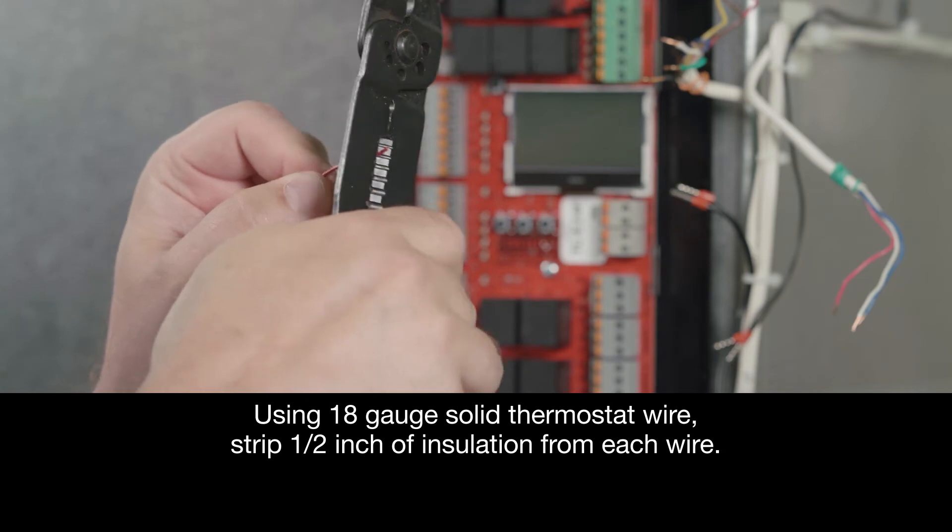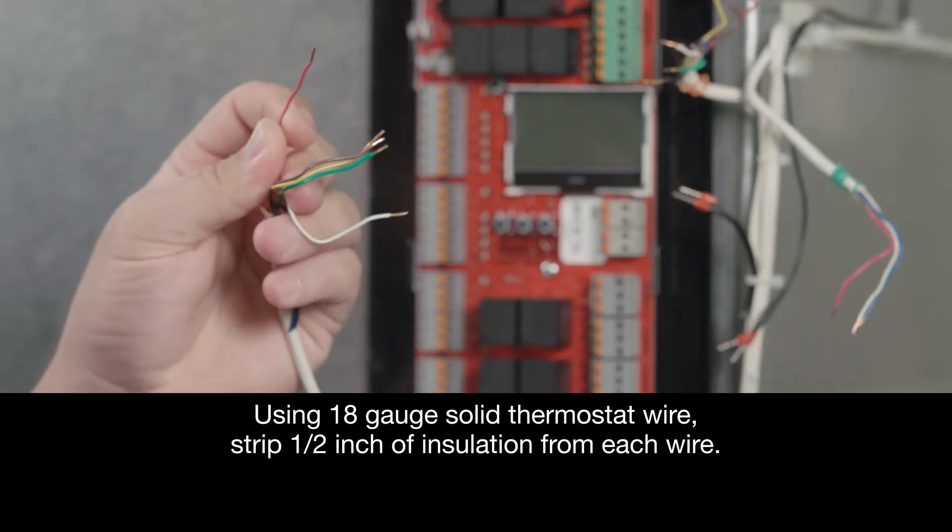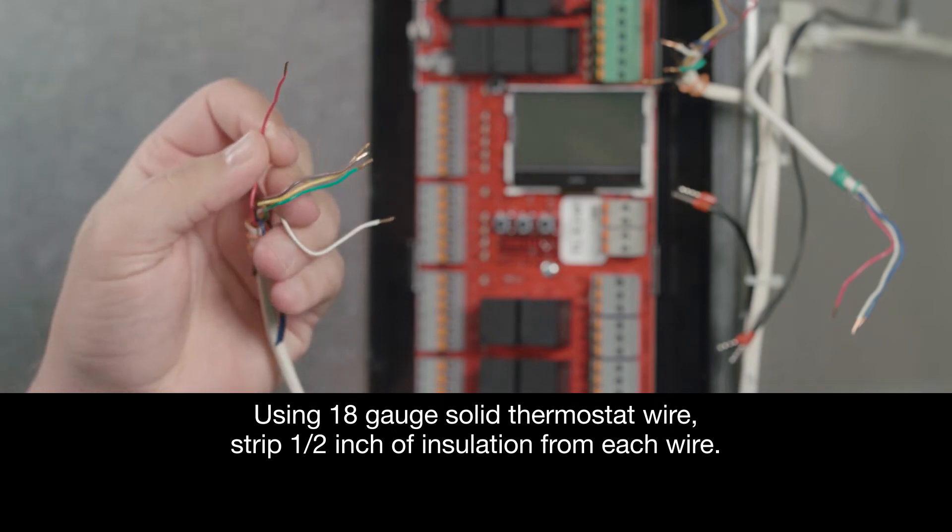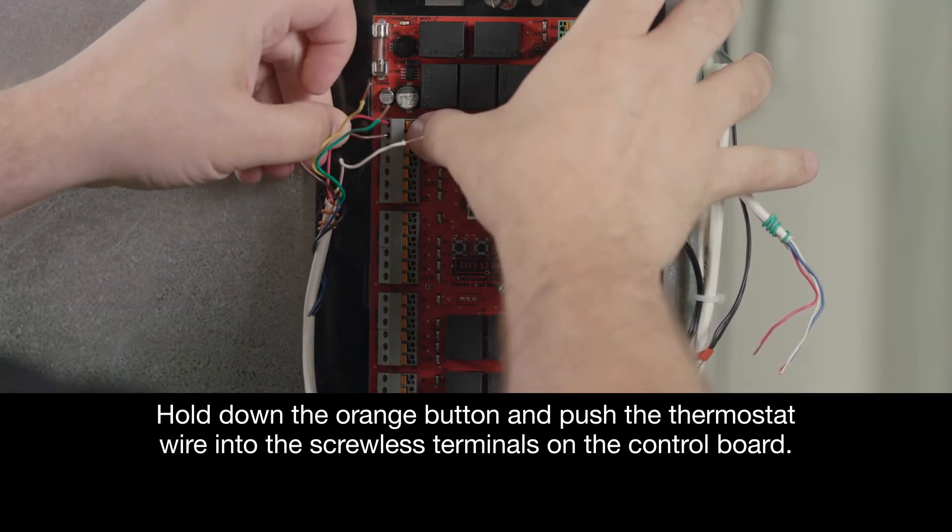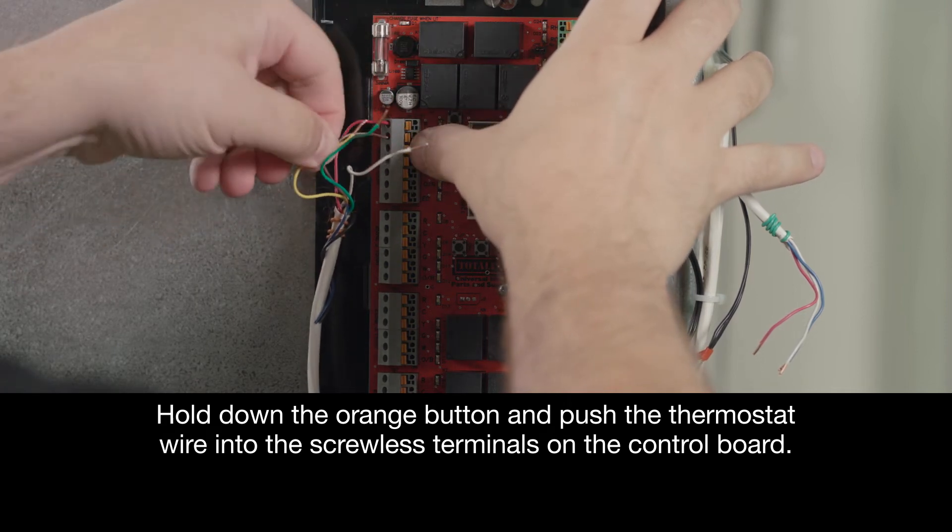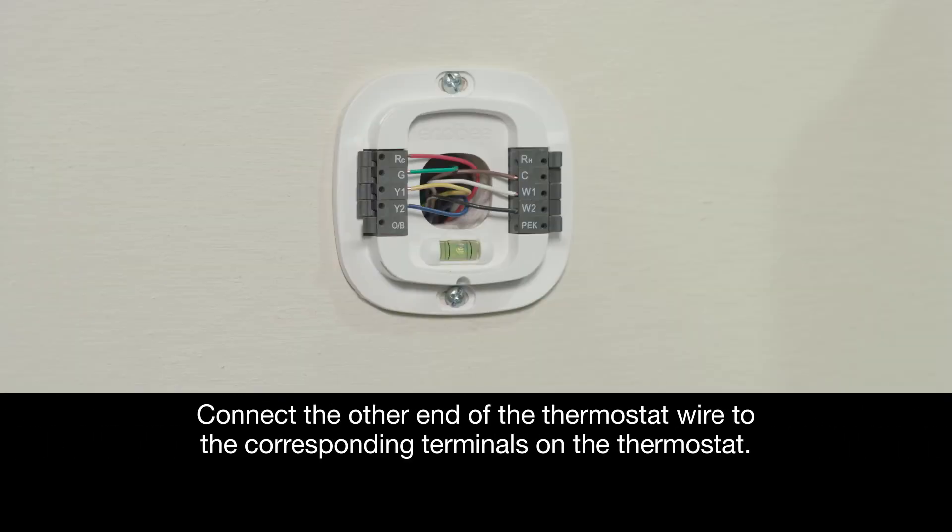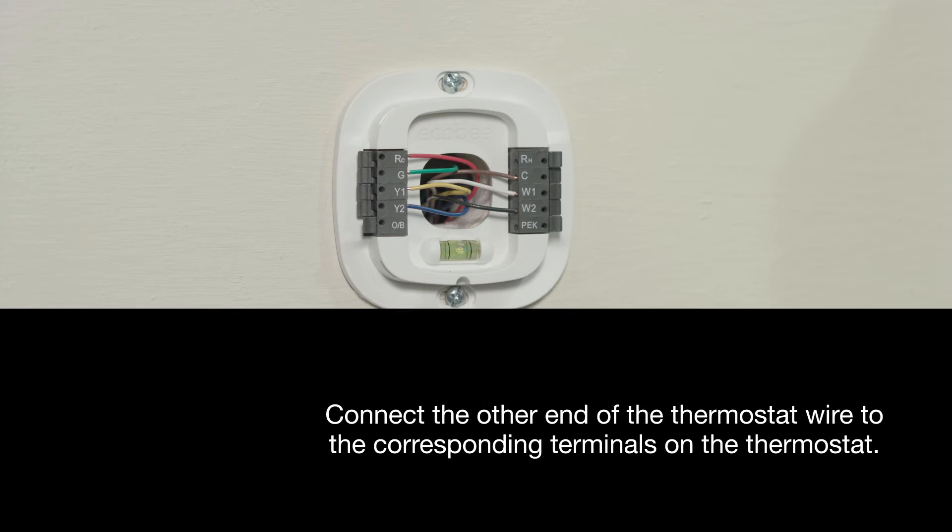Now, using 18-gauge solid thermostat wire, strip a half an inch of insulation from each wire. Hold down the orange button and push the thermostat wire into the screwless terminals on the control board. Then, connect the other end of the thermostat wire to the corresponding terminals on the thermostat.